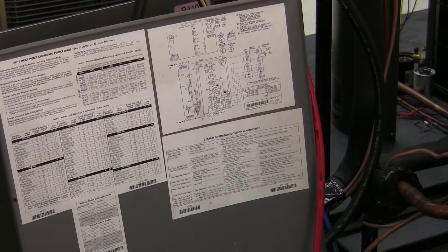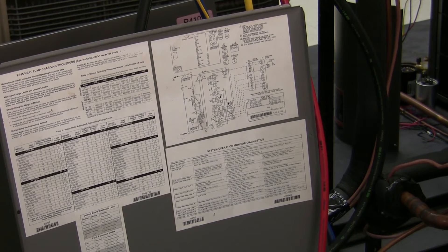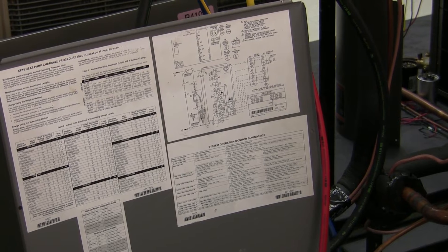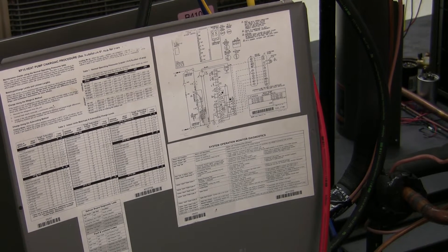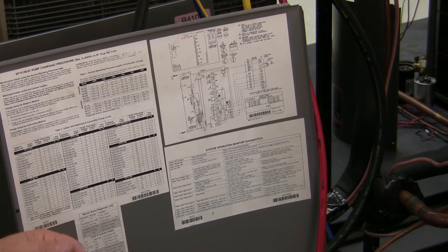Today we're going to talk about how to charge a Lennox heat pump in the heating mode. Most manufacturers will tell you that charging a heat pump in the heating mode is not possible. Here at Lennox, we tend to use thermostatic expansion valves at the indoor coil and the outdoor coil. We do not use accumulators, which allows us to charge by sub-cooling not only in the cooling mode, but also in the heating mode.